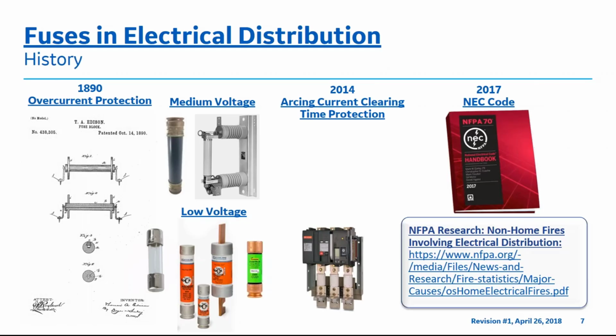The electrical distribution industry was provided with an industry-leading electronic device in 2014, which provides significant arcing current reduction for fuses. Prior to the 2017 NEC code, there was no enforcement of any type of arc energy reduction for fuses, and unfortunately, arcing faults have still led to accidents, fires, and sometimes tragic events. The 2017 NEC code has been adopted by several U.S. states and has begun to enforce and take the next step to solve arcing current problems for fuses.